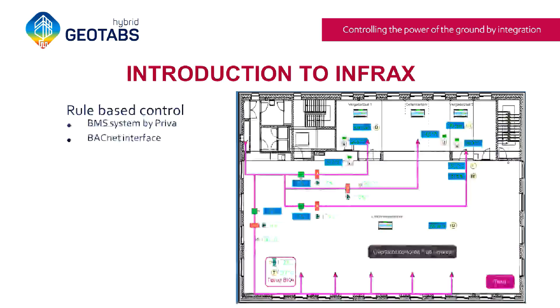So the building is currently controlled using a rule-based controller. It's a system of Priva. They have these graphical interfaces that look like this. It's very convenient for making adjustments. And it's controlled over a BACnet interface. So as Damien already explained, that's the interface that we try to hook up into. So we write directly on the BACnet layer to override the existing control signals. And that means we also have a fail-safe in case of problems, so we can fall back to the existing rule-based controller implementation.